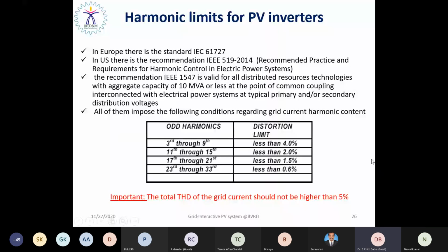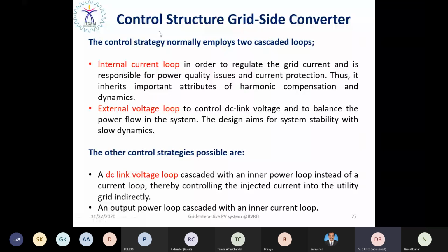Let us come to the control structure. The control strategy applied on this grid interactive power converter is very essential to meet the grid connection requirements. That control strategy is basically a cascaded control strategy, as it uses an internal current control and an outer voltage control. The internal current control loop is responsible for regulating the grid current, right? The grid current has to be controlled to inject only the sinusoidal current component, because the sinusoidal component is responsible for actual work in the grid, but other harmonic currents should be rejected at this stage.